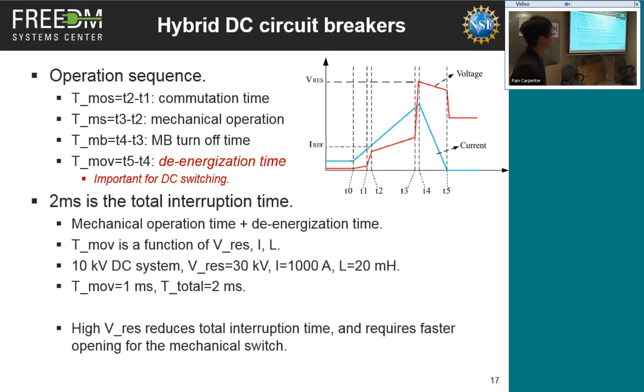TMOV is a function of the residual voltage, also the current and the system inductance. The current and the inductance are system parameters, and from a circuit breaker design point of view, you cannot change them. But you can make the residual voltage higher, and that has something to do with the speed of the mechanical switch. So the faster your mechanical switch is, the shorter the time you'll need to interrupt this DC circuit.